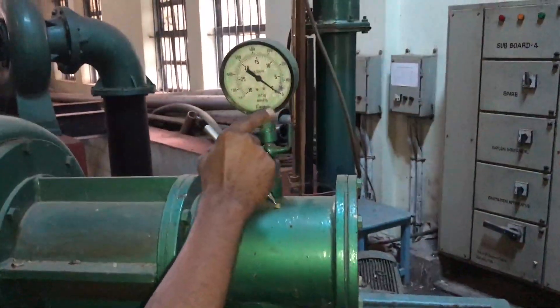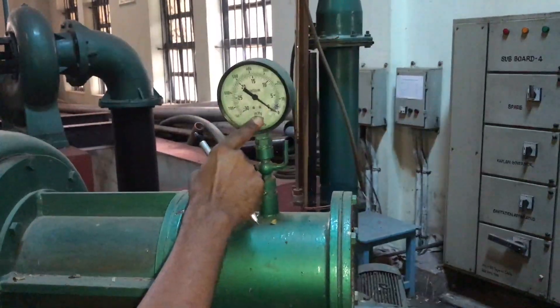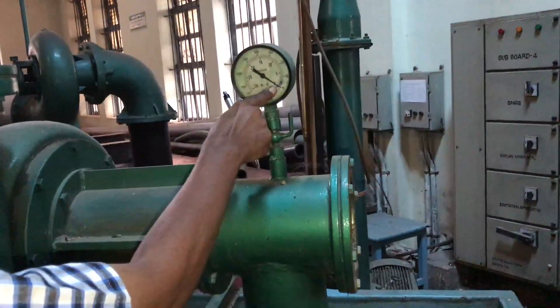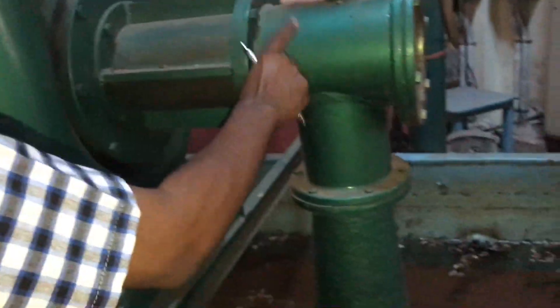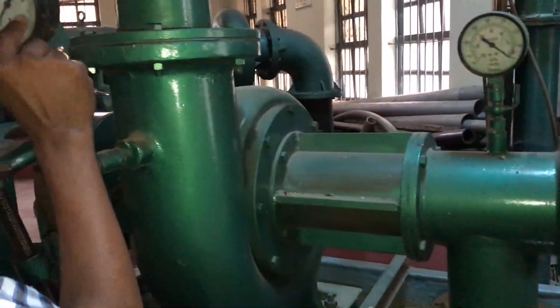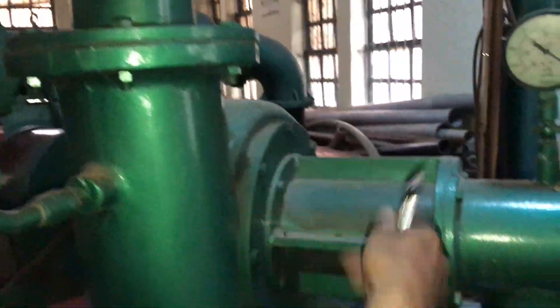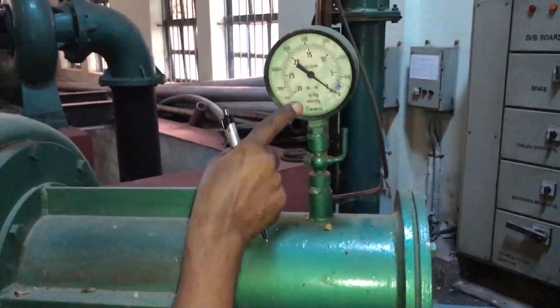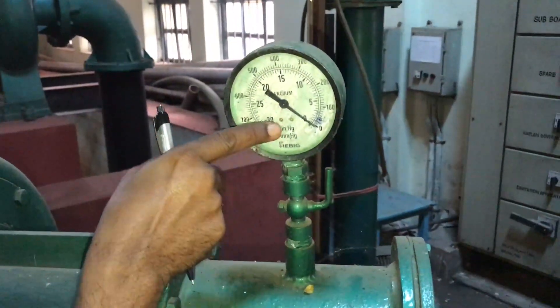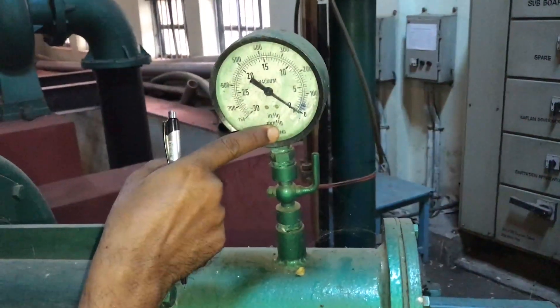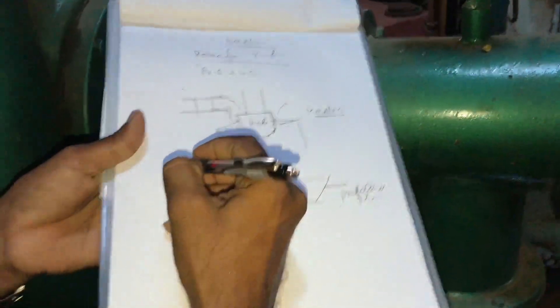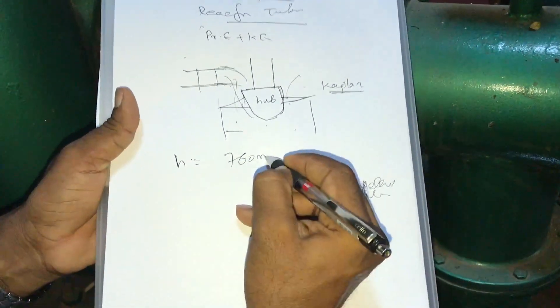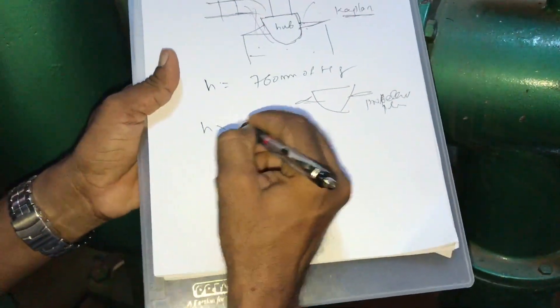A vacuum gauge is connected here because the pressure at the exit is less than atmospheric. In the case of a pump, there is a vacuum gauge on the suction side and a pressure gauge on the delivery side. But in reaction turbines, the inlet pressure head is higher and goes on decreasing, so the exit pressure is less than atmospheric — hence a vacuum gauge is connected. The vacuum gauge reads in mm of mercury. The atmospheric head is 760 mm of mercury.